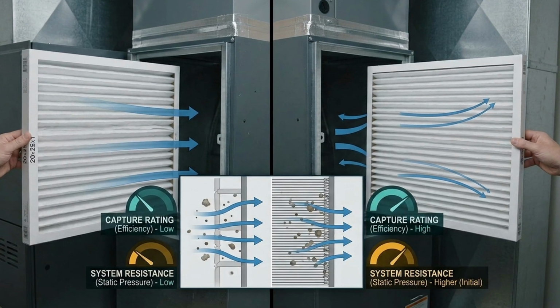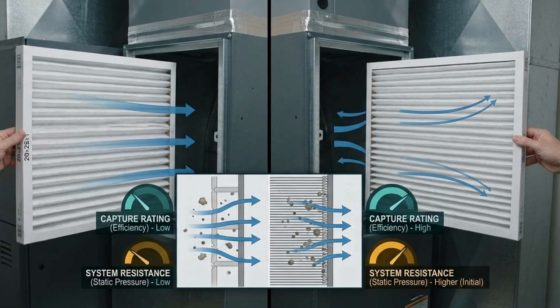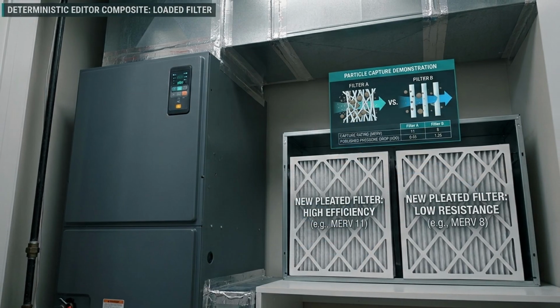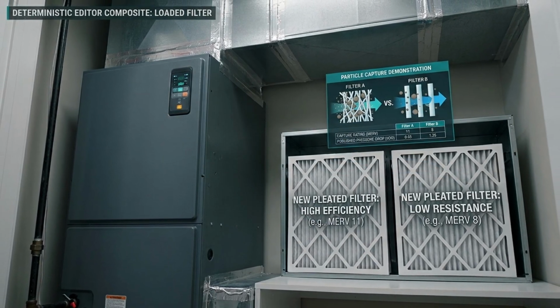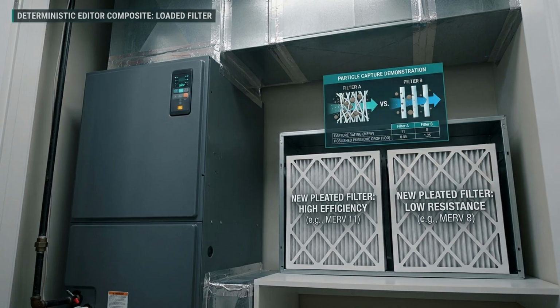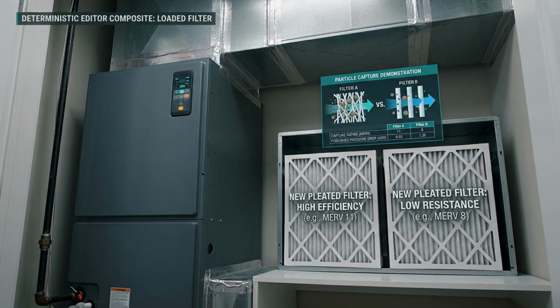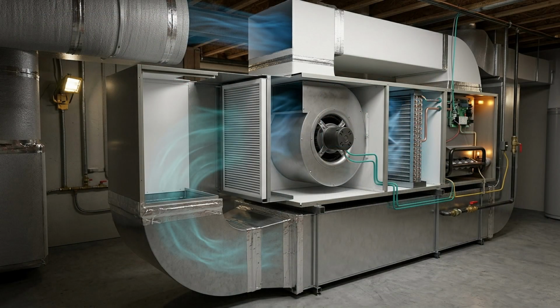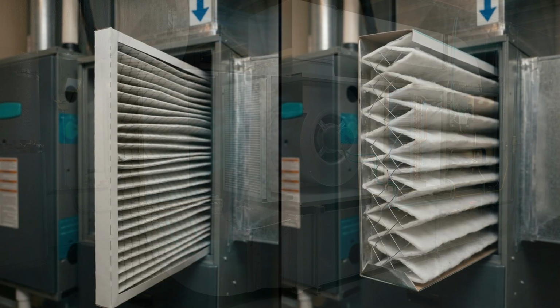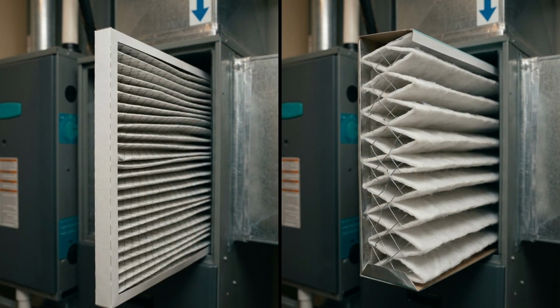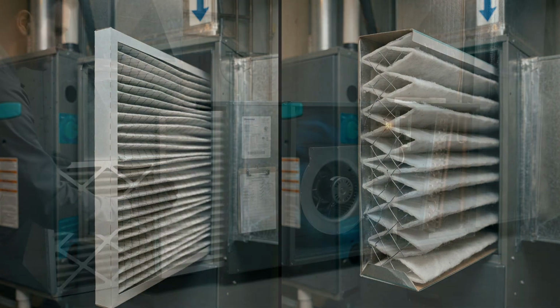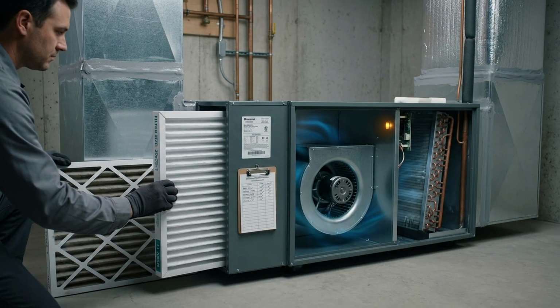A loaded lower MERV filter may create more resistance than a clean, well-designed higher MERV filter. That does not create one universal replacement interval. A home with renovation dust, pets, heavy outdoor smoke, or long equipment runtime may load a filter differently from another home. Follow the equipment and filter documentation, inspect at the recommended interval, and replace based on the documented condition or schedule. Do not run the system without a filter to see whether the airflow feels stronger. That can move debris into equipment and does not provide a safe operating solution.